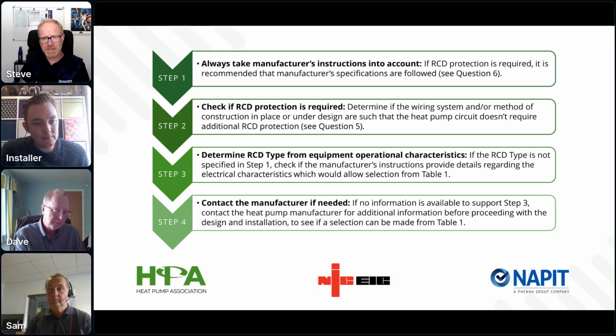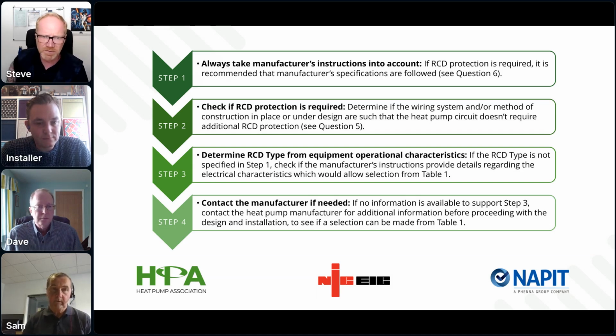So there is actually a product safety standard, which is BS EN 60335-2-40. Now that covers RCD selection for heat pumps in quite a bit of detail, and air conditioning units and other things. But it's worth noting that is a product standard rather than an installation standard. And we're in a world now, I think Sam will agree, where sometimes the product standards cross over into installation standards and installation standards cross over into product standards. But we've got to be clear that, like we've just said, there is nothing specific in the wiring regulations that relates.